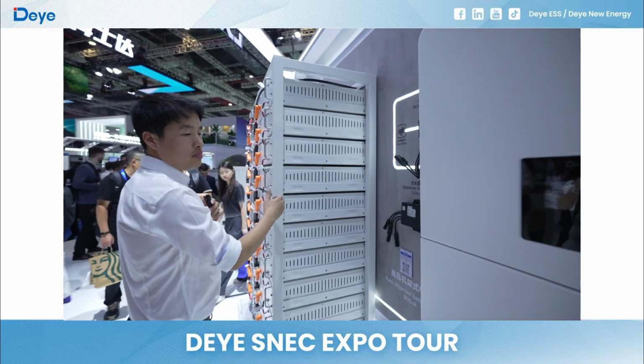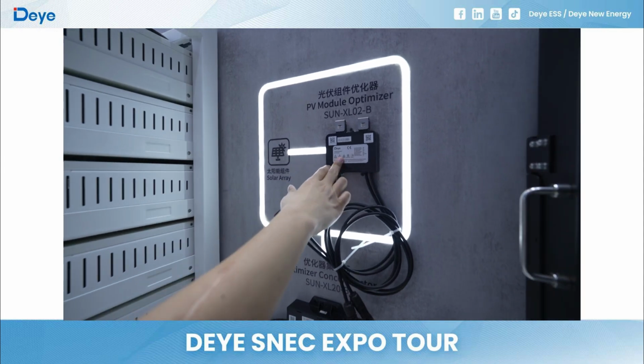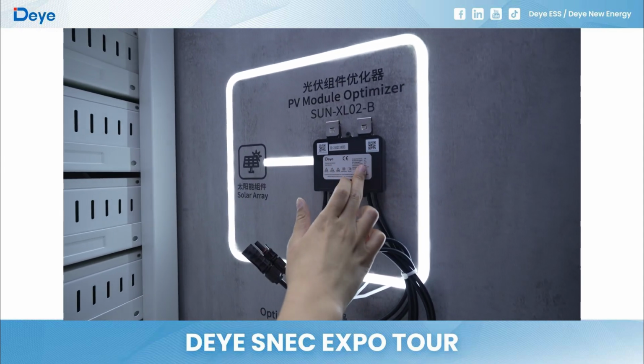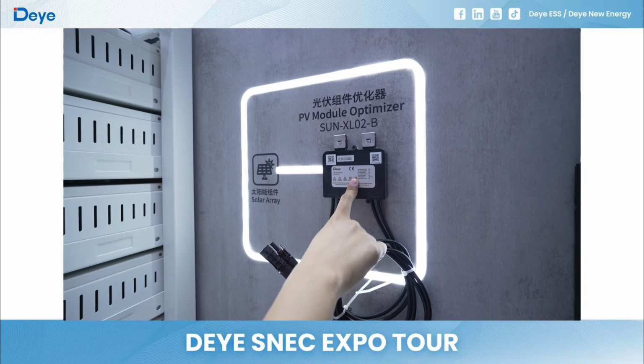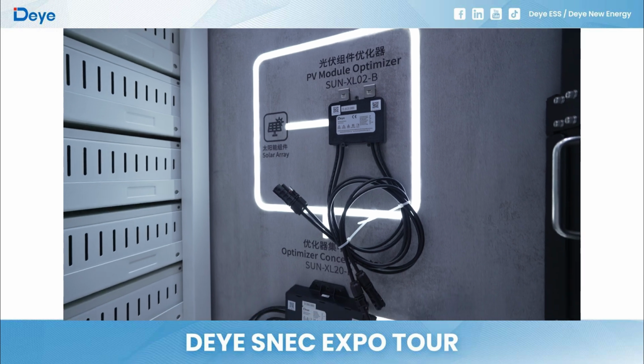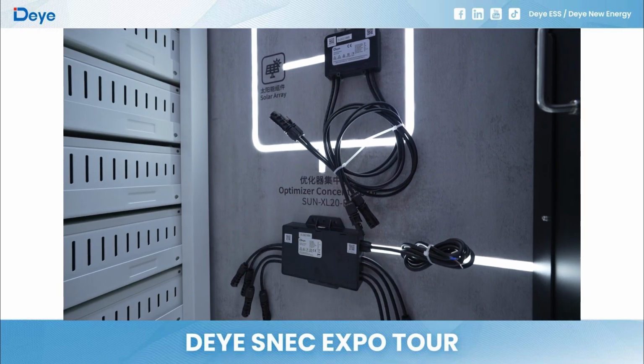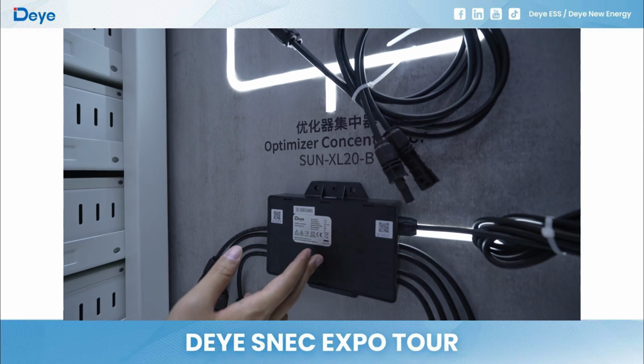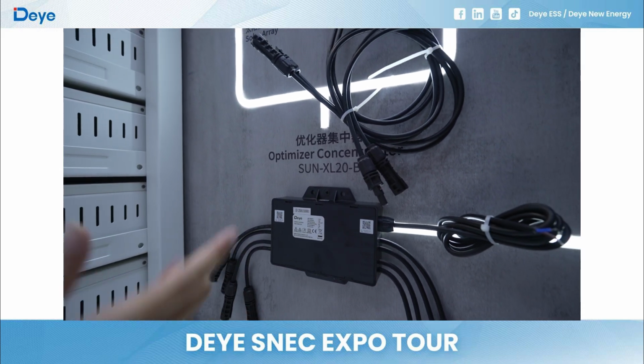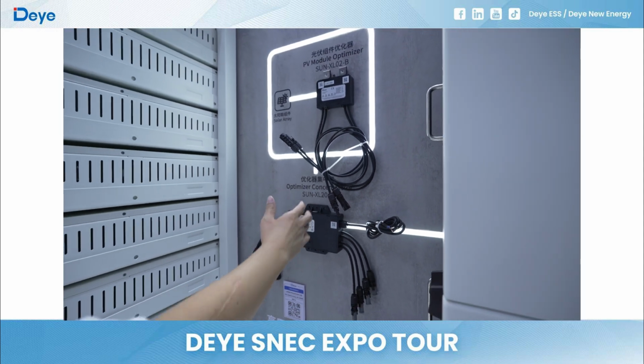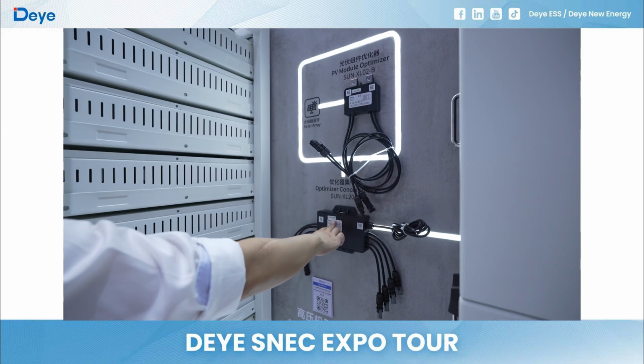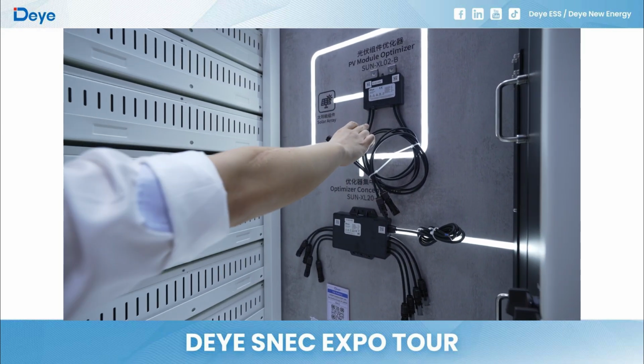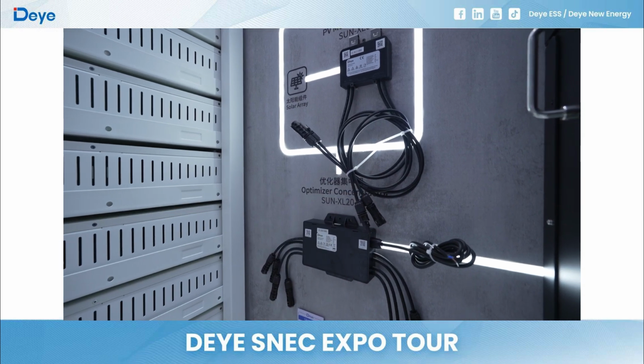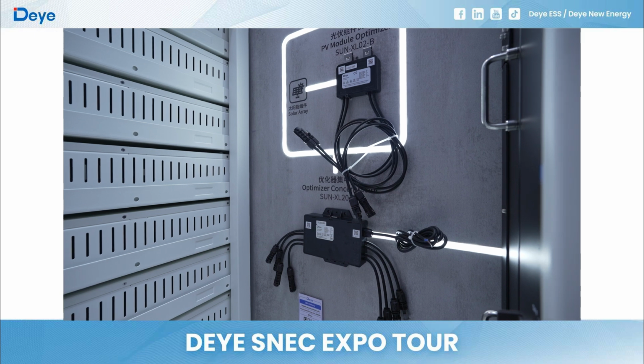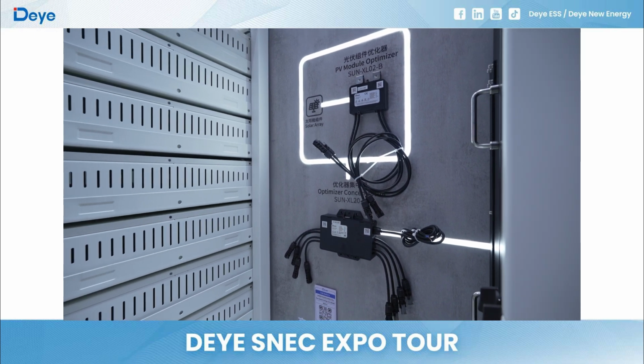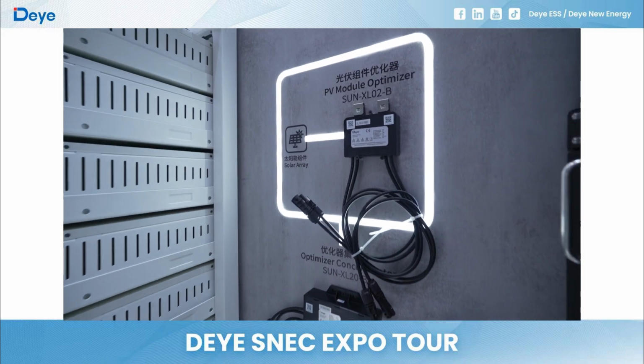Okay, move here. We can see we install a solar PV module optimizer here, and the rated current is 50 amps. This is the optimizer concentrator. This concentrator can connect a maximum of 25 solar optimizers. When there is an emergency situation, the concentrator can turn off the optimizers very fast and safely. For example, when there is a fire, it will make sure the fire won't affect the AC side.